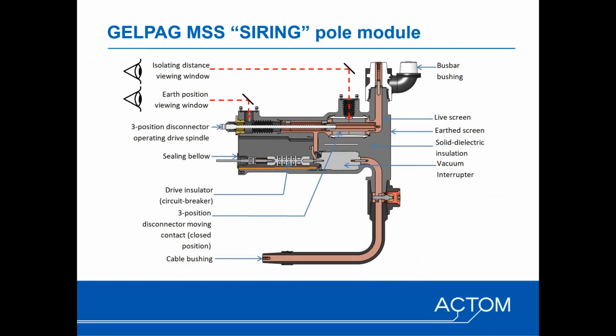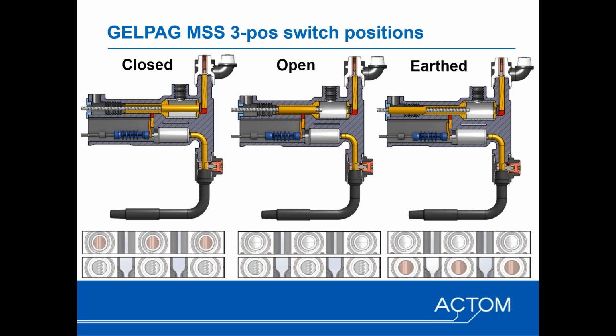This is just a side view, and we have included this presentation in the handout, so I won't go through every component, but just show some of the key features, as well as the ability to have visual confirmation of the isolating distance. This is often problematic with fixed pattern switchgear, because you don't have the withdrawable circuit breaker and therefore no visual confirmation. This provides visual confirmation through a special viewing window and mirrors, and you can then confirm, in addition to the mimic diagram and position indicating devices, the actual status of the 3-position switch. These slides just show those 3 positions.